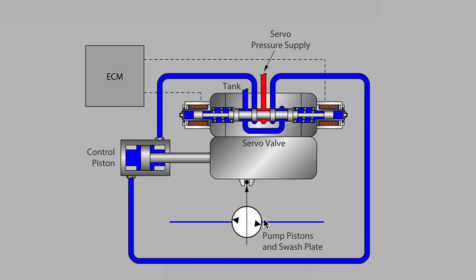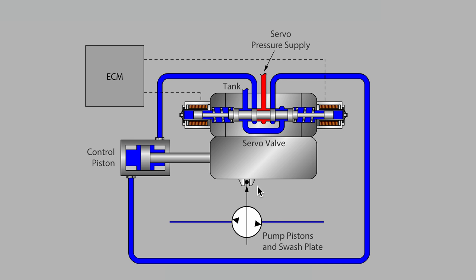The internal pumping elements — the rotating group made up of pistons in a cylinder barrel — are shown here using the simplified circle symbol. The long arrow cutting through represents the swashplate in the piston pump. Changing the position of the swashplate will represent changes in flow direction and flow volume.